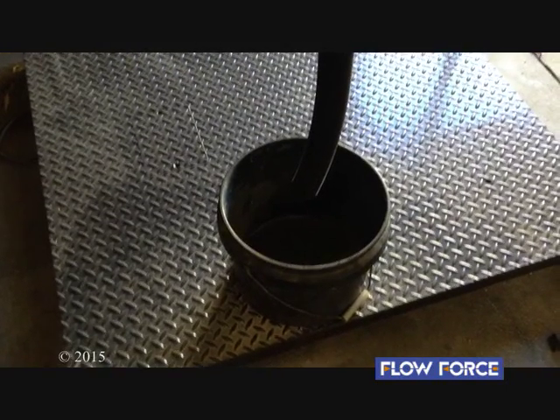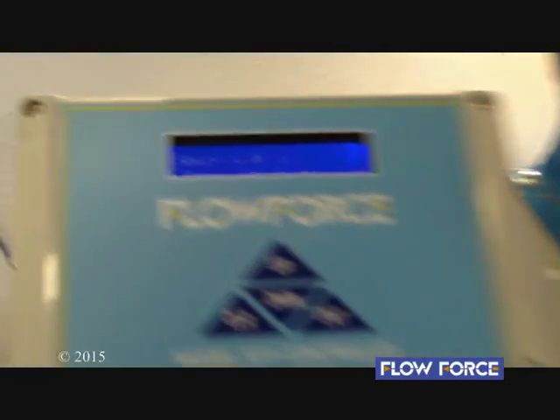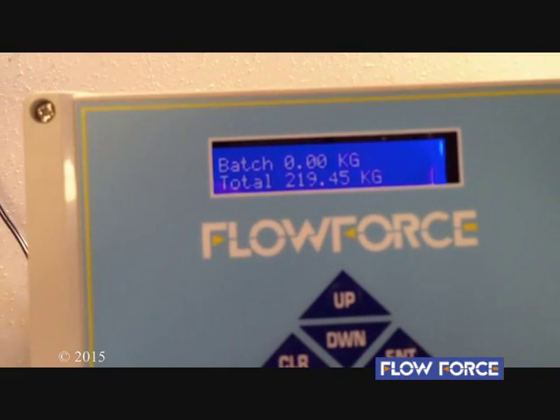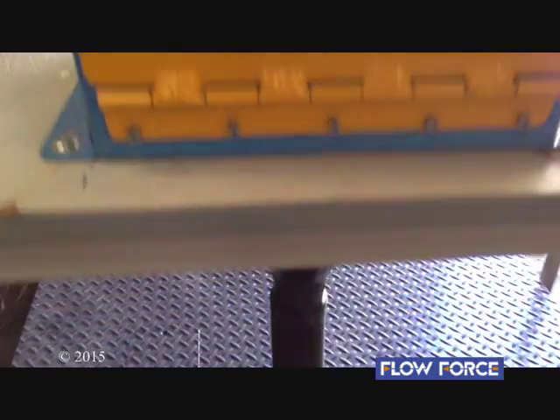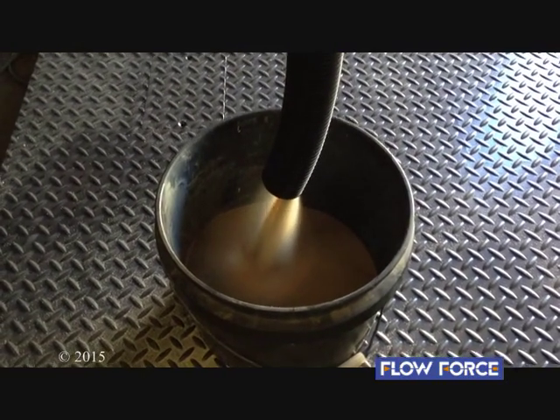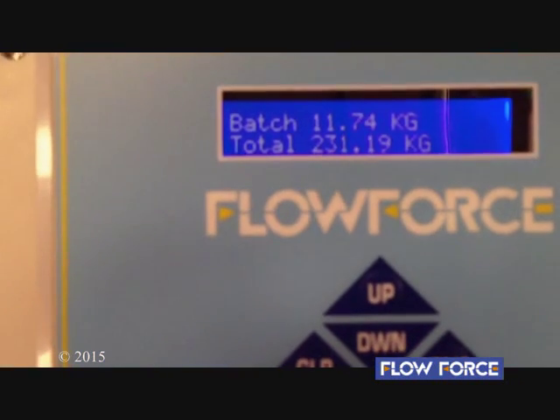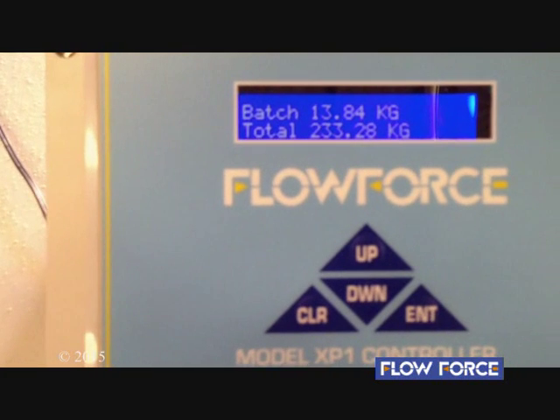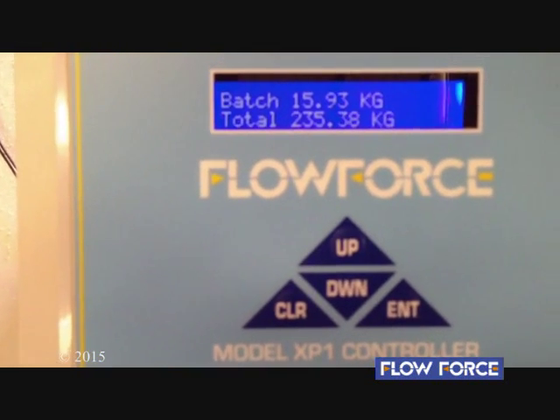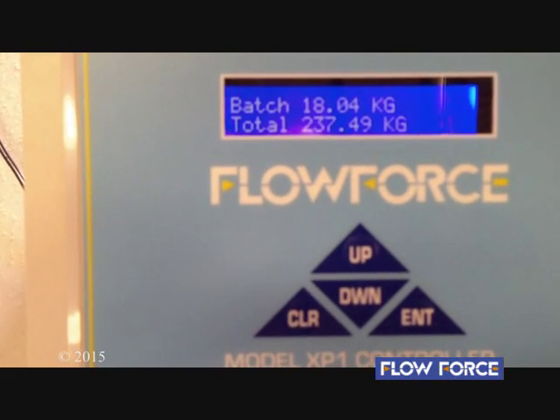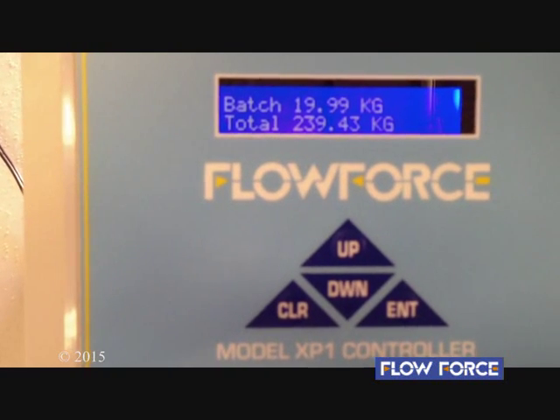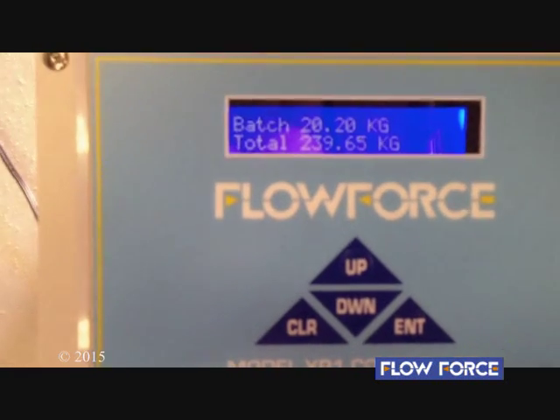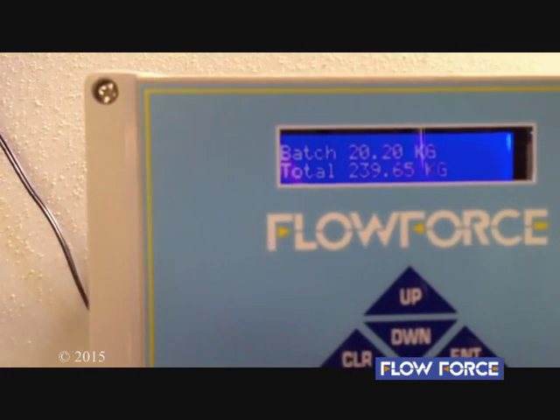We set up for test number 3. We have the bucket underneath the impact plate. We've zeroed our batch. We can now start to feed for batch number 3. See the sand flowing through on the impact plate, down into our test container. And our controller is reading the actual weight. So looking at this, our controller is reading 20.2 kilograms.